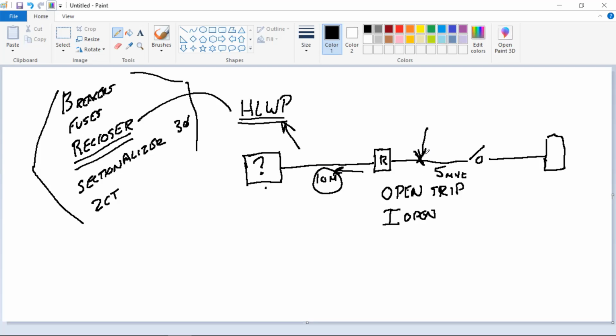So a fault occurs down here, you've got a hotline work permit. When a fault occurs, it's going to open immediately. So what we discussed before, you've got to watch out for reclosers also while you're closing fuses down here anywhere in this section of the line on this circuit. You can get hotline work permits on just the recloser itself.